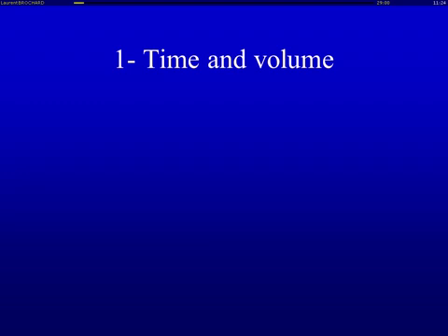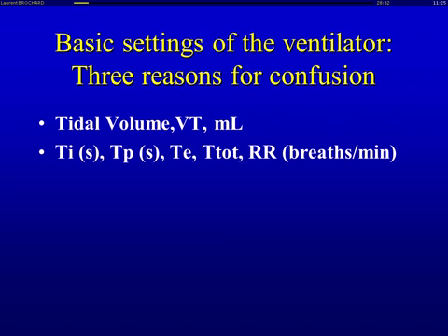The first issue: you have to be very familiar with time and volume when you deal with ventilator settings. You deal with time and volume, and the relationship between volume and time is called flow. The ventilator needs to know which flow to use to deliver a given tidal volume. That's why you cannot set the ventilator with only tidal volume and respiratory rate — you also have to tell it how long the insufflation should be. This is the insufflation time, which is sometimes different from the inspiration time, which adds the pause to the insufflation.